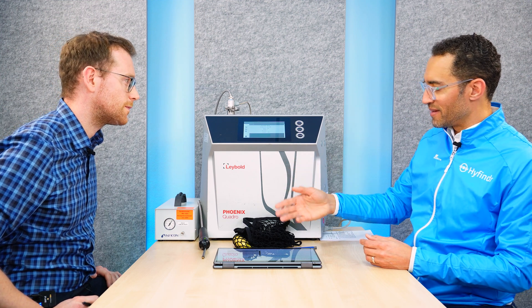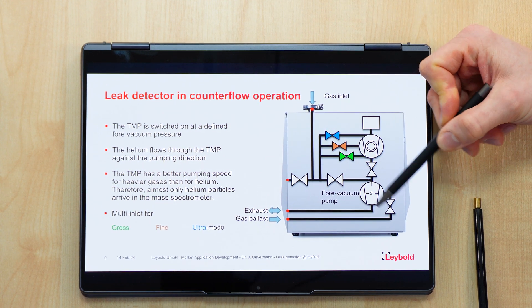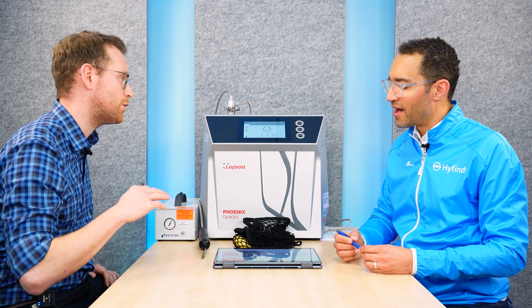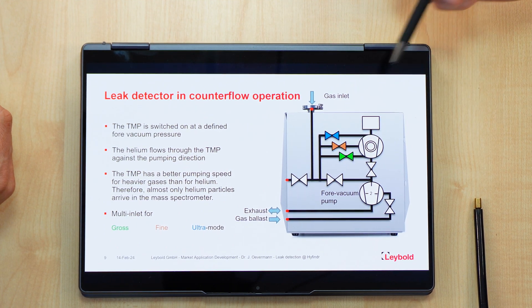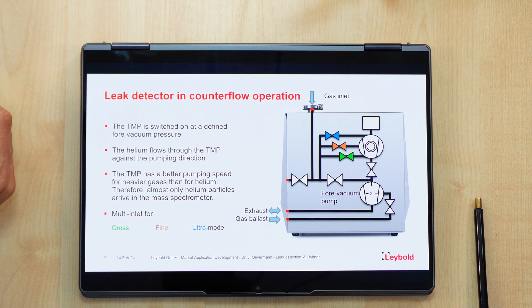It's essentially like a vacuum cleaner. Why is it that big? We have our mass spectrometer here, plus a turbo molecular pump and a fore vacuum pump — a backing pump — and you always need both of them. The turbo molecular pump is comparable to the engine of an airplane — it's a centrifugal device used to produce a very good vacuum, at pressures below around 1×10⁻⁴ millibars. You need very low pressures for the mass spectrometer to work. It's a high vacuum pump which always needs a backing pump, which is also included, and that's one reason why it's that big.